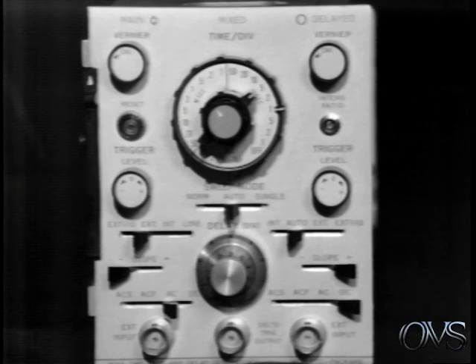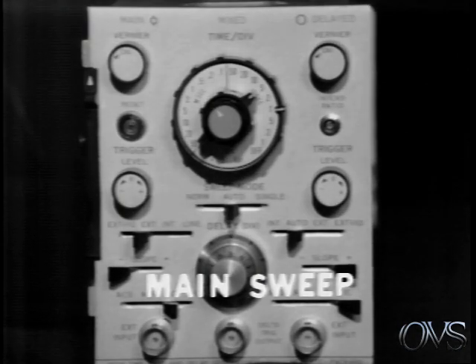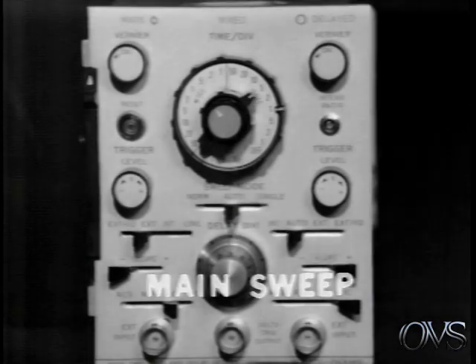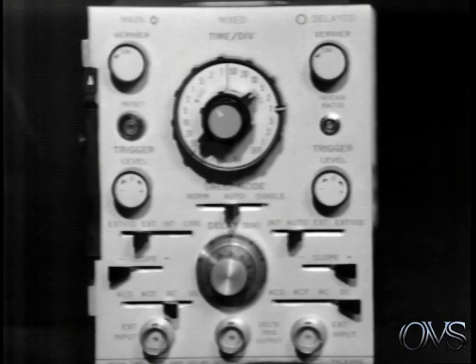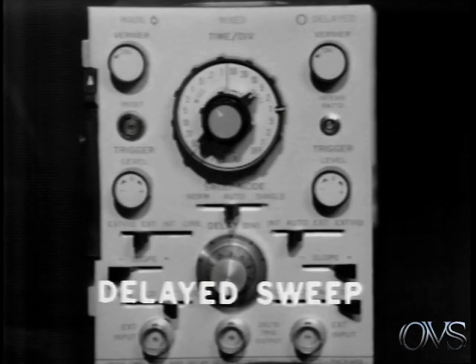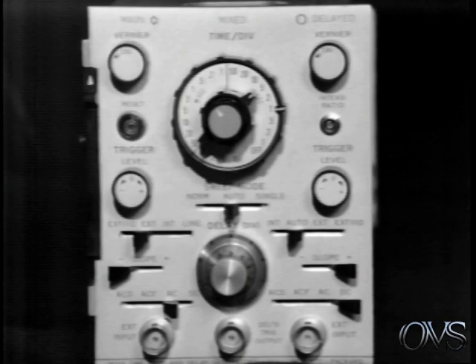You will recall from the 180 operation tape that a delayed time-based generator requires two linear sweeps. The first is called the main sweep. And in delayed sweep applications, the main sweep is used to precisely set the delay interval. The second sweep is called the delayed sweep. And this sweep is actually used to drive the horizontal deflection system, providing the calibrated time base of the CRT display.